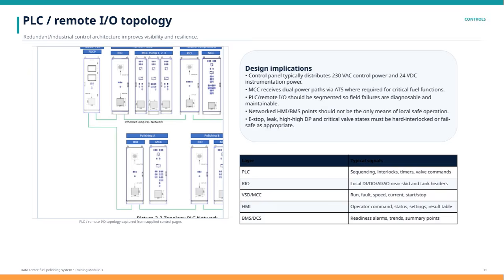Looking at the design implications, the control panel typically supplies 230 volts AC for control power and 24 volts DC for instrumentation power. For critical fuel functions, motor control centers receive dual power paths through an automatic transfer switch, ensuring continuous operation even if one power source fails. Segmenting the PLC and remote I/O is crucial. This segmentation allows any field failures to be quickly diagnosed and maintained without affecting the entire system.